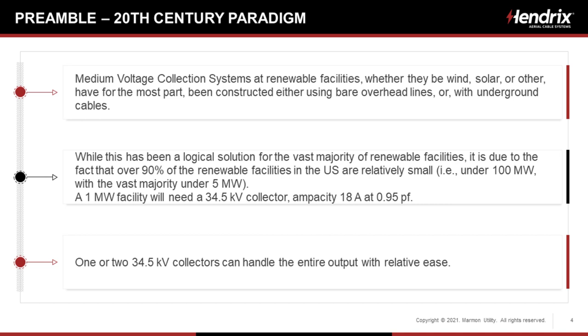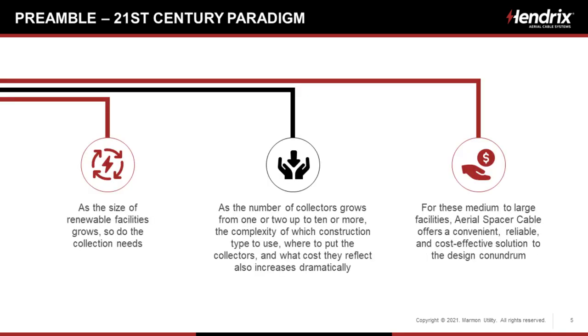As an electrical design engineer, if you look at a 1 megawatt facility with a 34.5 kV collector system, you bring it back at 18 amps. Even if you've got a 5 megawatt facility, you've only got 90 amps. I mean, you can bring that in with an overgrown extension cord. So one or two 35 kV collectors can handle the entire output of 95% of these facilities with just a single collector.